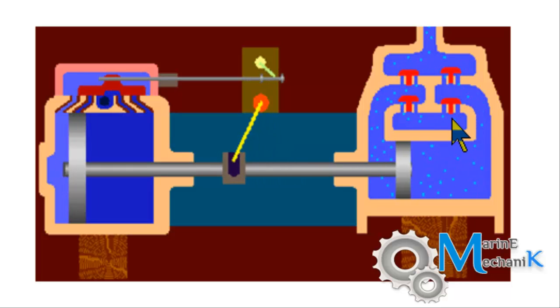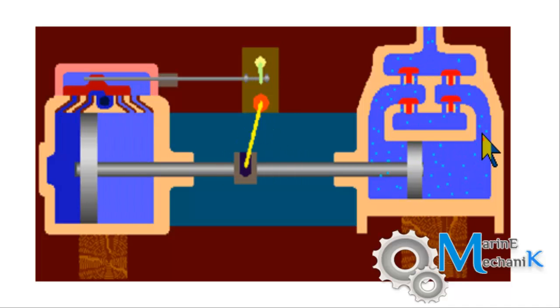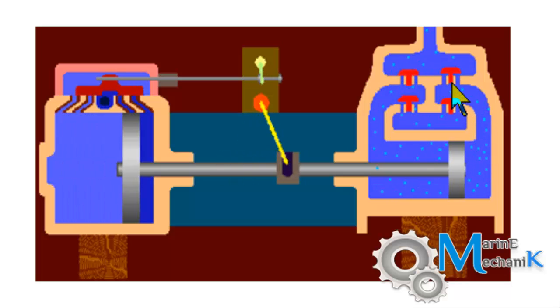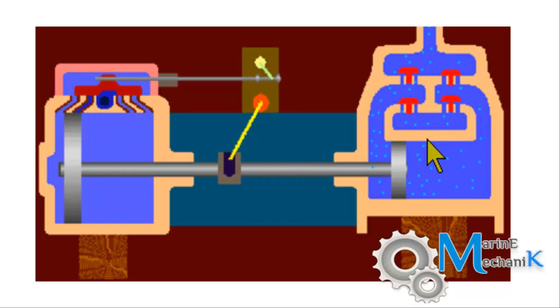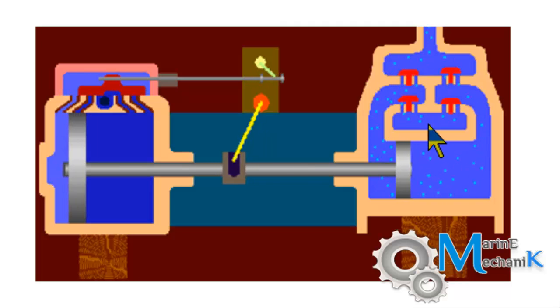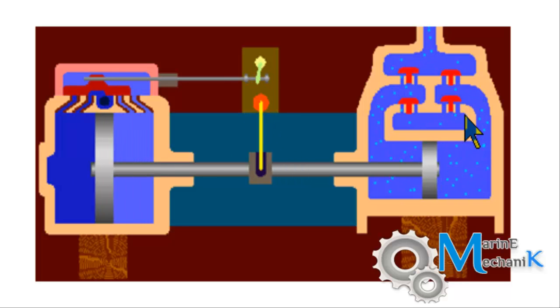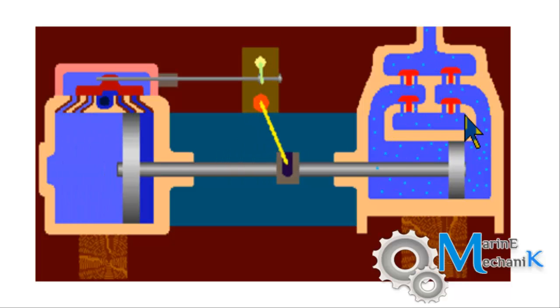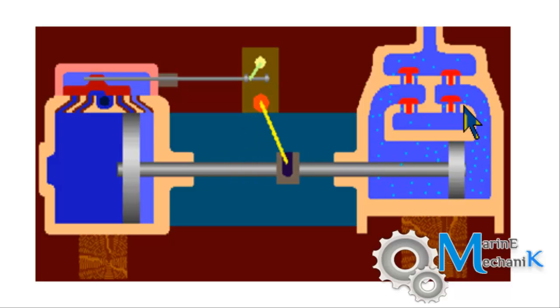When the piston moves from BDC to TDC, one of the suction valves lifts and then the water from the suction valve chest fills the chamber. Then as the piston moves from TDC to BDC, it lifts the discharge valve and goes to the discharge chamber. Since there are two suction valves and two discharge valves with one piston connected to a common chamber, this will give more output or throughput than the normal one which has single piston single valve on suction and delivery. This is a typical animation of a simple reciprocating pump which is of steam operated type.